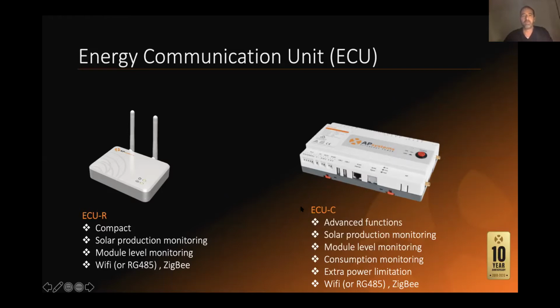You can add current transformers (CTs) to monitor production and consumption in the house. I know in Australia, in certain states, you need zero injection to the grid, so the ECU-C can pilot zero injection. As soon as your PV produces more than the load in the household, the ECU-C will gradually shut down micros by steps of 50 watts to make sure you never inject the excess into the grid.